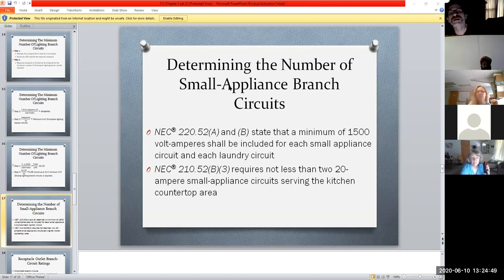Then we look at the number of small appliance branch circuits throughout the house. Very typically that's the kitchen. The kitchen runs several of our small appliances: microwaves, toasters, coffee makers, and all that. Pound for pound, the kitchen has the most small appliances compared to the rest of the house. Others you might have are bathroom areas or occasionally a utility room, but very commonly the kitchen is considered your small appliance room, if you will. If we look at the NEC, there are a couple of articles we have to deal with. They state that a minimum of 1,500 VA shall be included for each small appliance circuit and each laundry circuit.